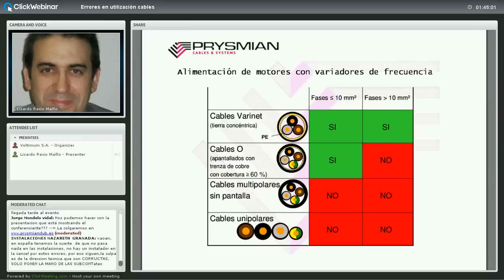Tabla resumen: para motores hasta 10 mm² de sección se puede admitir un cable con pantalla de trenza de cobre (cobertura >60%) y la tierra como conductor adicional. Para fases de más de 10 mm² se debe usar siempre el cable Varinet, que vale para cualquier potencia. Nunca cables sin pantalla ni cables unipolares para alimentación con variadores de frecuencia.